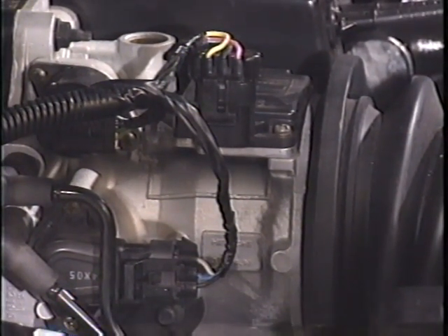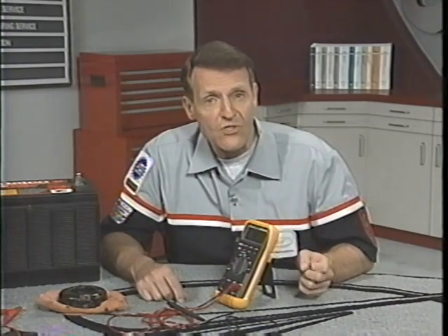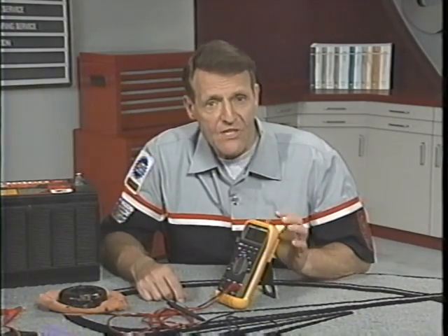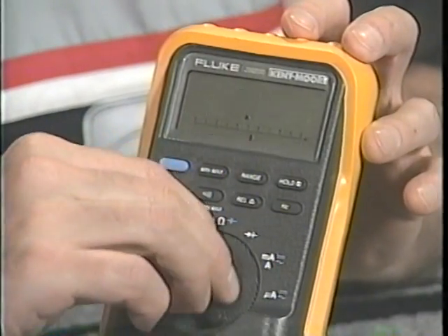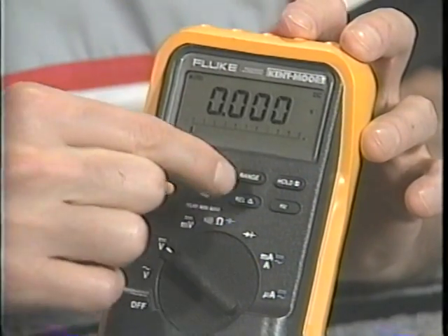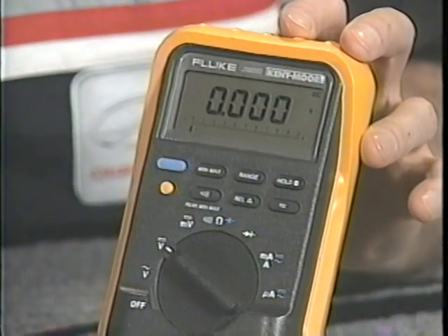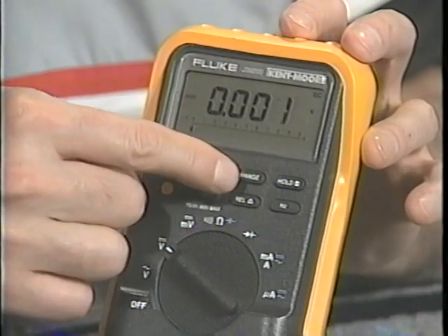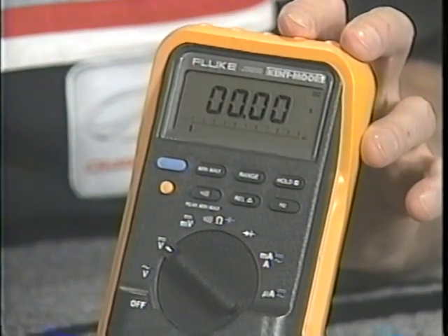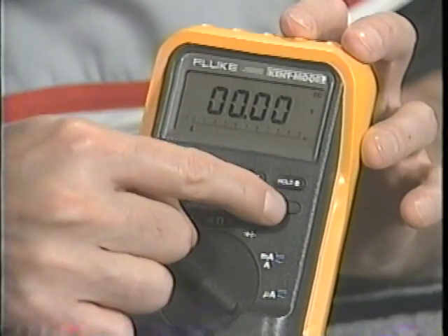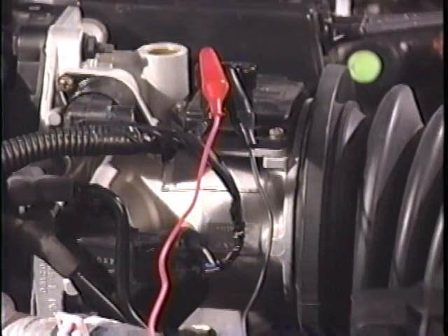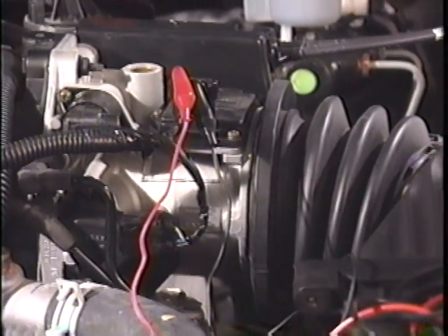voltage. To check whether the frequency is changing smoothly, you can set the meter to DC volts, exit from auto range, and select the 40 volt range. Then press the Hertz button.